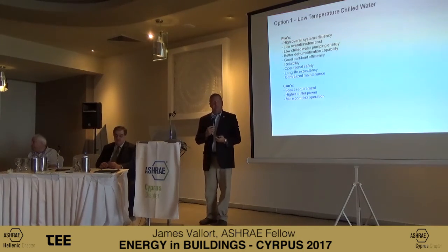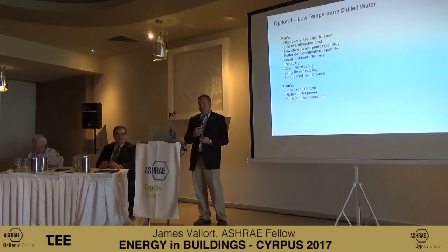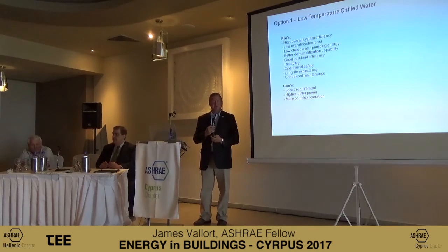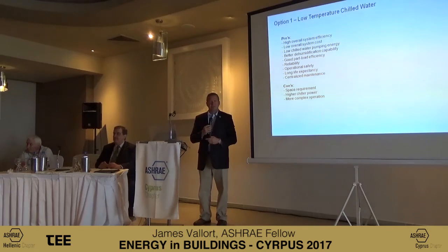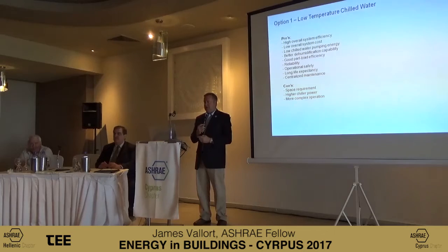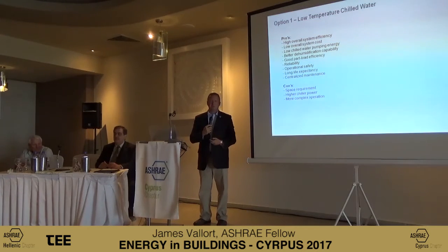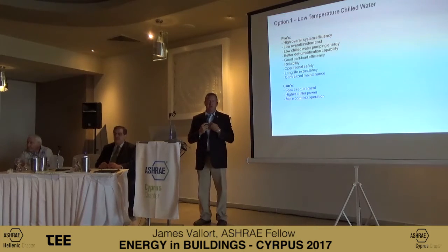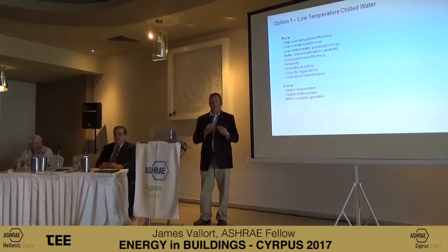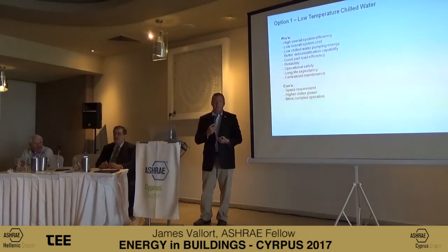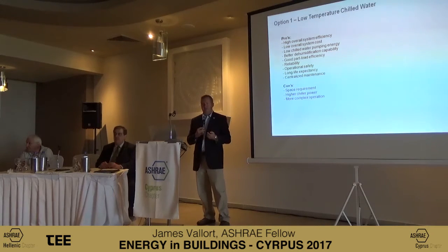The low temperature system has interesting pros and cons. It has lower system cost and better dehumidification — in humid climates, that lower temperature really brings moisture out. One of the biggest cons is that it's more complex. As designers, we hand our building over to an operating staff who may not have chosen to step out of their comfort zone. If you give them a system that's more complex, we need to make sure they understand it and run it as intended. Otherwise, we end up with a beautiful system they run just like their last one.